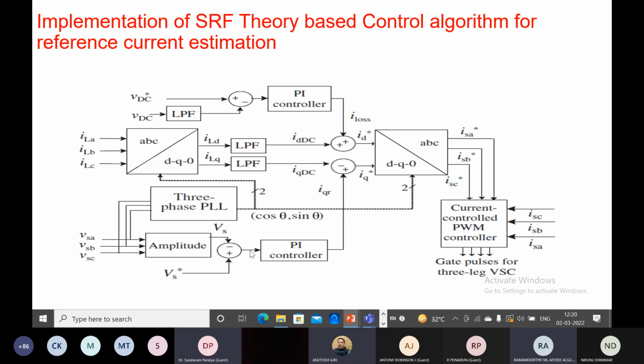So how to calculate the voltage error? VSA, VSB, VSC can be sensed from the supply system through voltage sensors, and the amplitude will be calculated. VS equals 2 by 3 - there is a formula in my papers as well. Vs equals under root of 2 by 3 times VSA square plus VSB square plus VSC square.